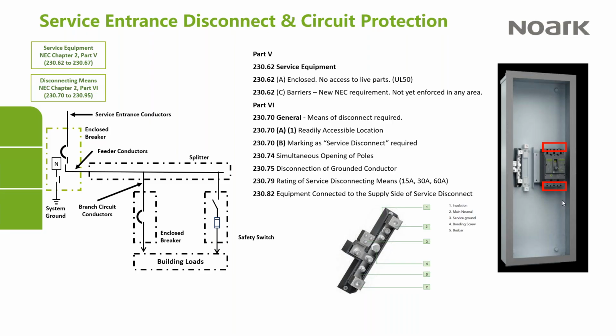To our knowledge, it's not been enforced in any state yet. But what it means is that we will have to add an accessory to our breakers that provides this barrier so that you can't contact live parts that are on the utility side of the disconnect.